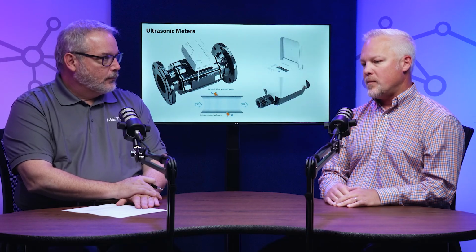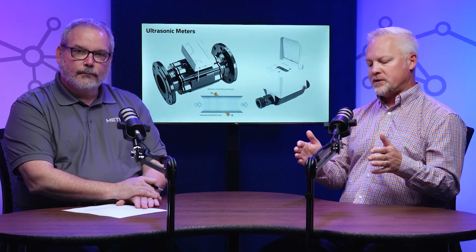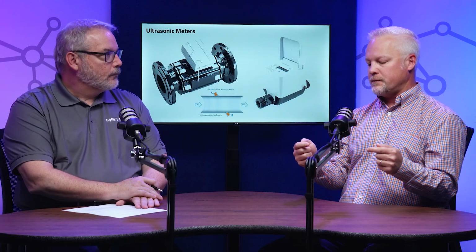So actually, a fairly easy device to understand. So you have at least one pair of transducers. A transducer is, think of it like a combination speaker and microphone, because you have to be able to go in both directions. So basically you have those transducers in the flow of water, and you're just sending signals back and forth. So ultrasonic, meaning just above human hearing. A lot of times it's sort of in the 1 megahertz to 2 megahertz range is what the frequency of that signal going back and forth is.